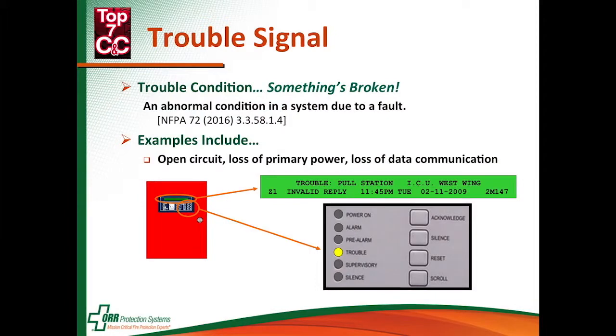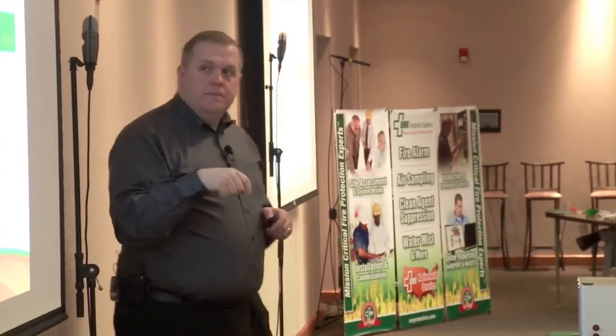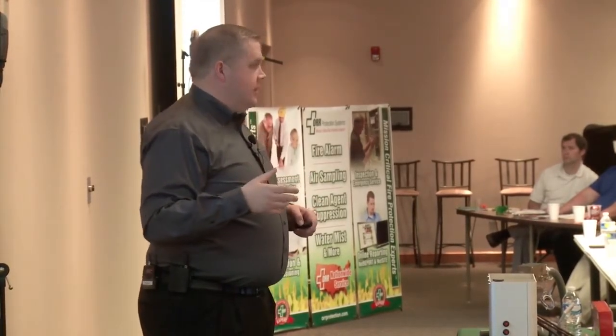Trouble conditions mean that there's something wrong with the fire alarm system itself. At the panel, for example, with this green display, it says we've got a trouble with the pull station ICU West Wing — it's got an invalid reply. So there's a problem with communication between the pull station out in the field back to the panel. And here we've got a little yellow light lit up next to the word trouble, as well as the piezo on the panel going off, making that annoying little noise.